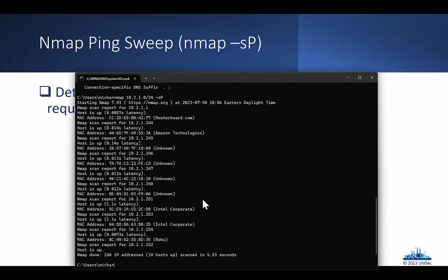Again, this is one that is more than likely safe at higher levels of the Purdue model, but as you get lower, it's not necessarily always safe, even if we think, oh, it's just an ICMP packet. If those remote hosts, especially the older ones, don't understand how to interpret that incoming ICMP request, it could crash, it could die, you could brick it to where you have to replace it, and that's not the type of day anybody wants to have.